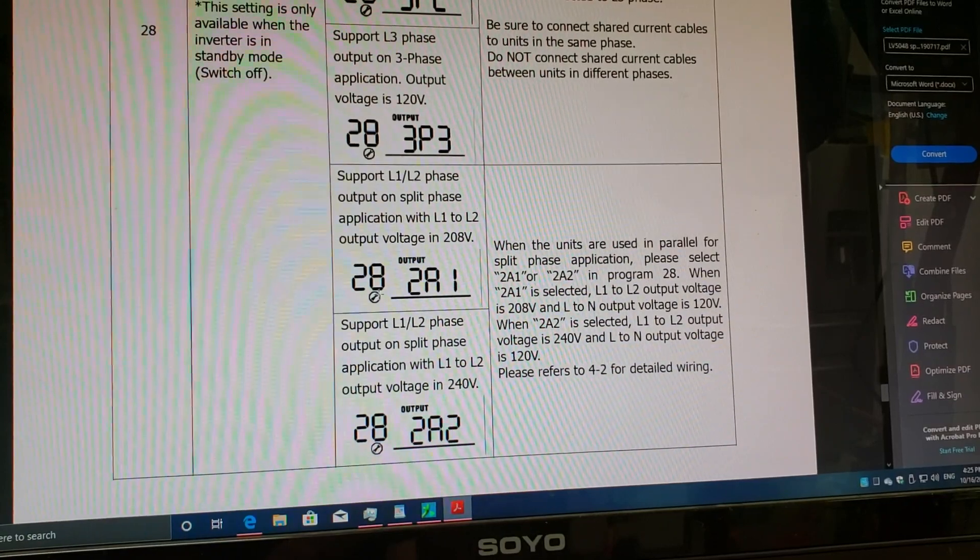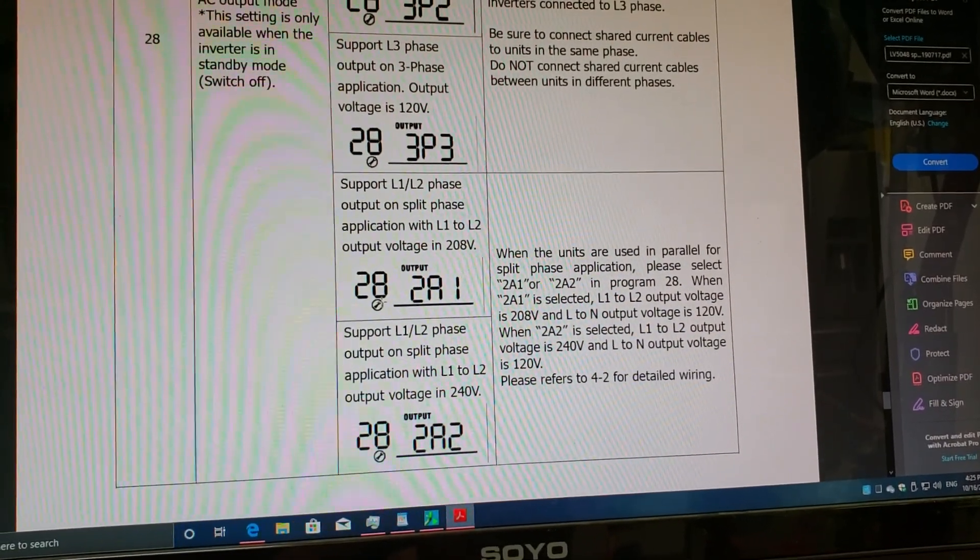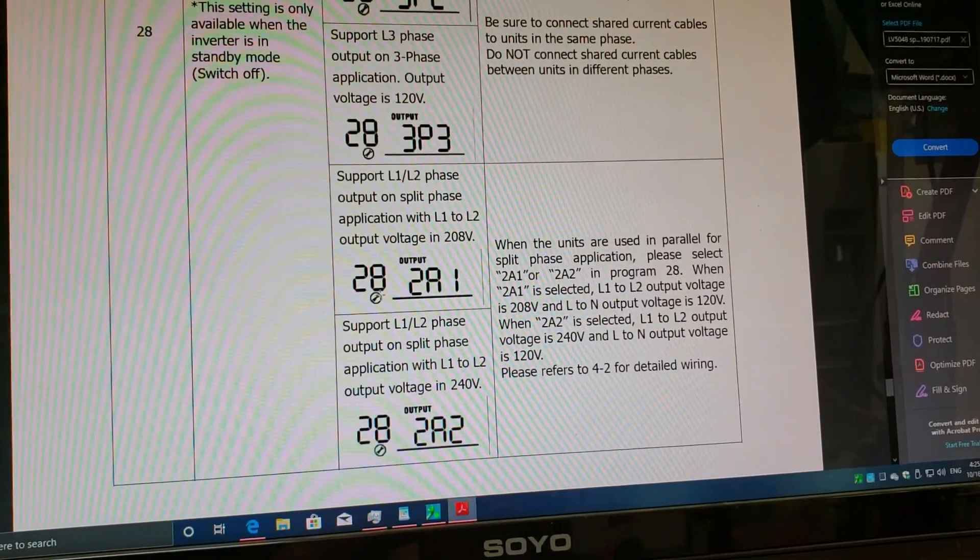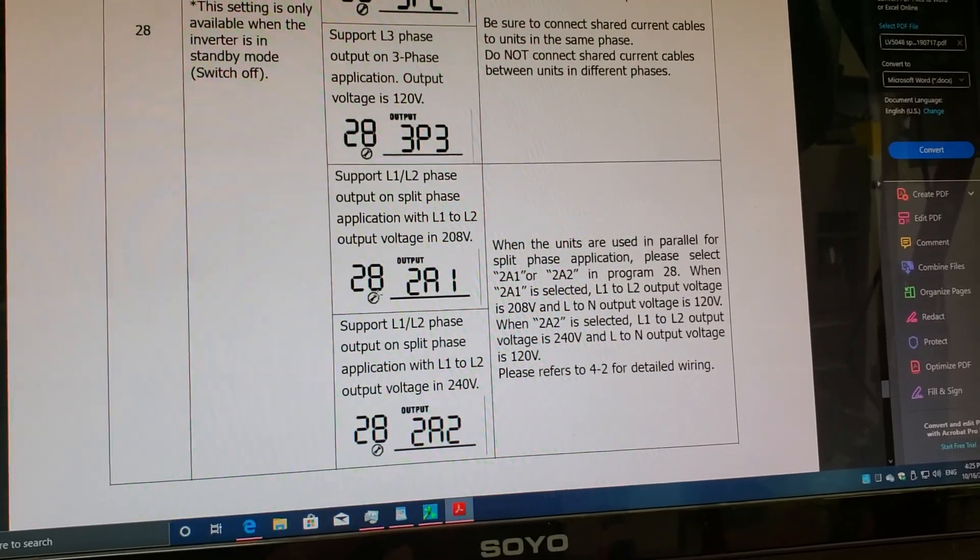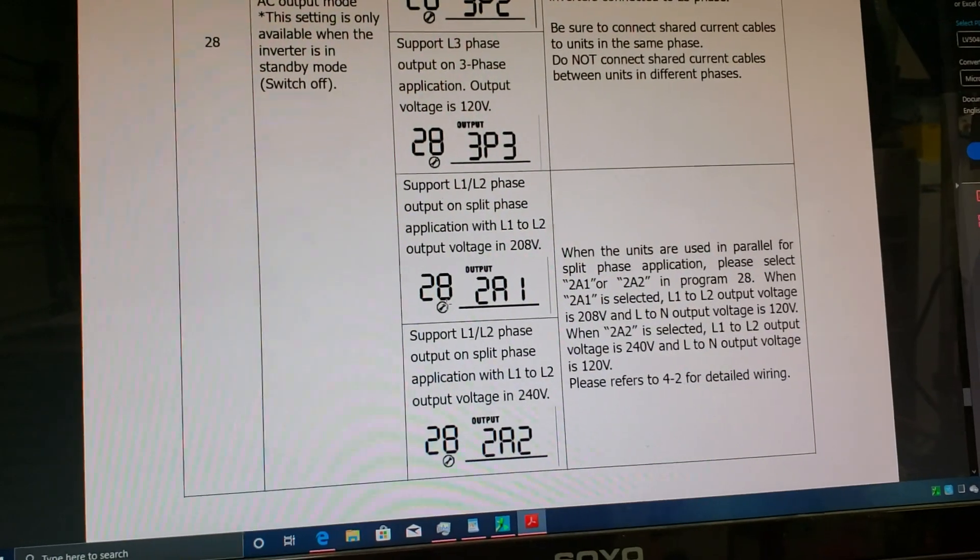I did the same thing for inverter number two. I turned it on, then turned it off, went into programming menu number 28, and changed the output of the unit for split phase 240 volt setup to a 2. After that, the unit shut down.